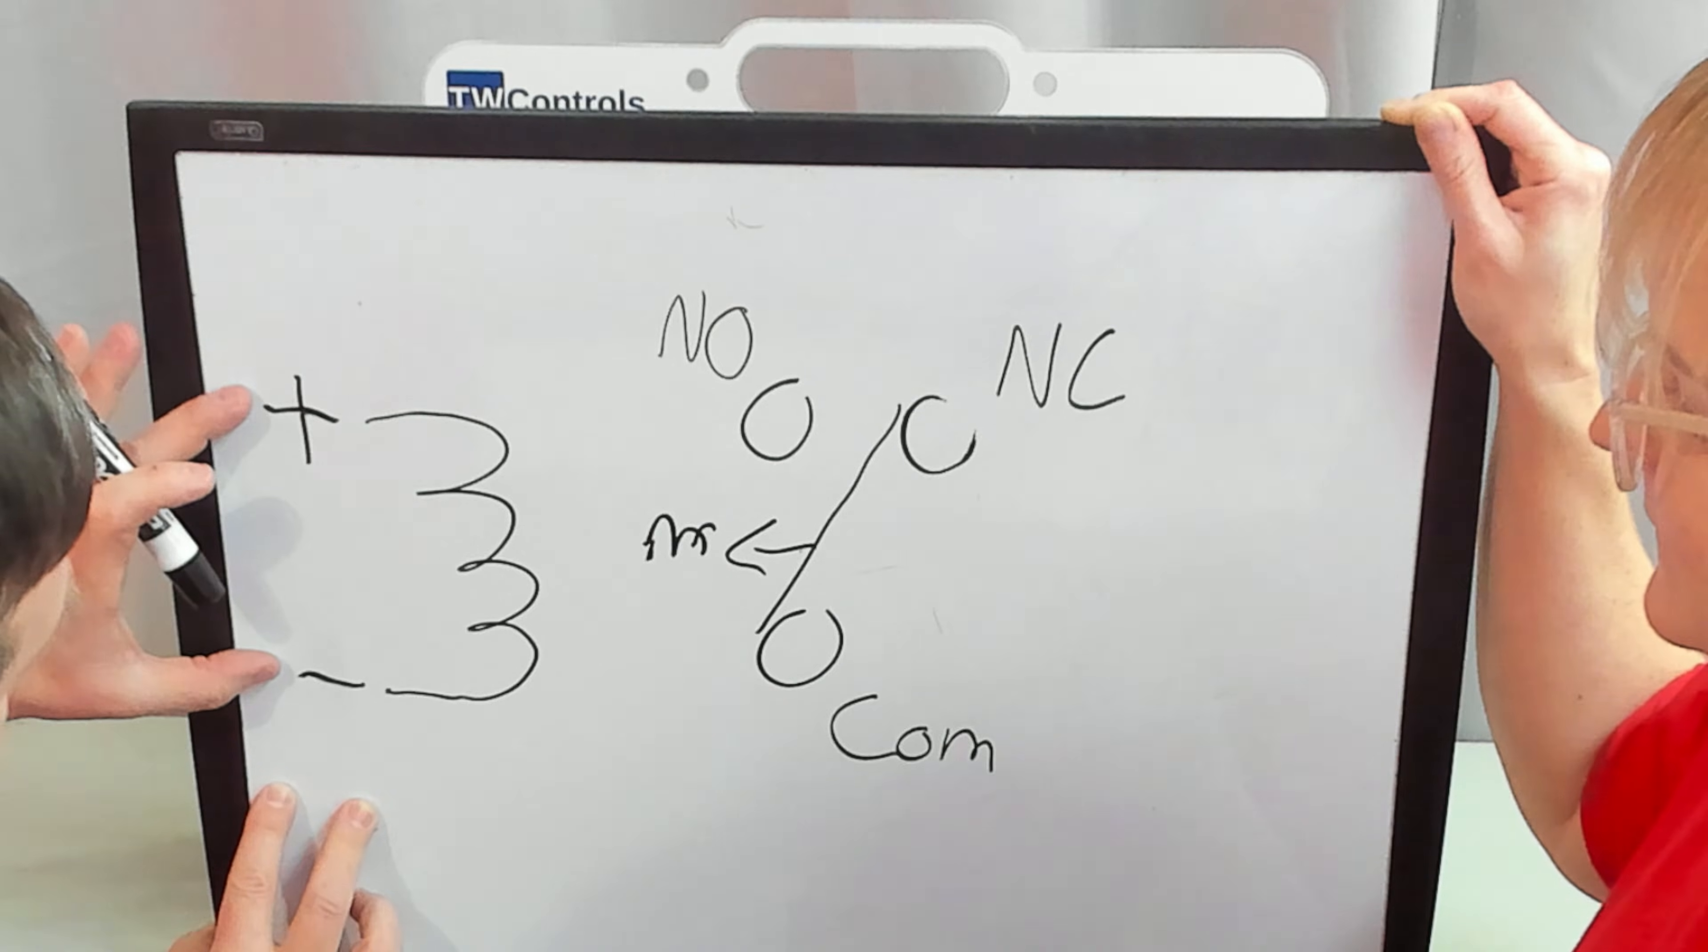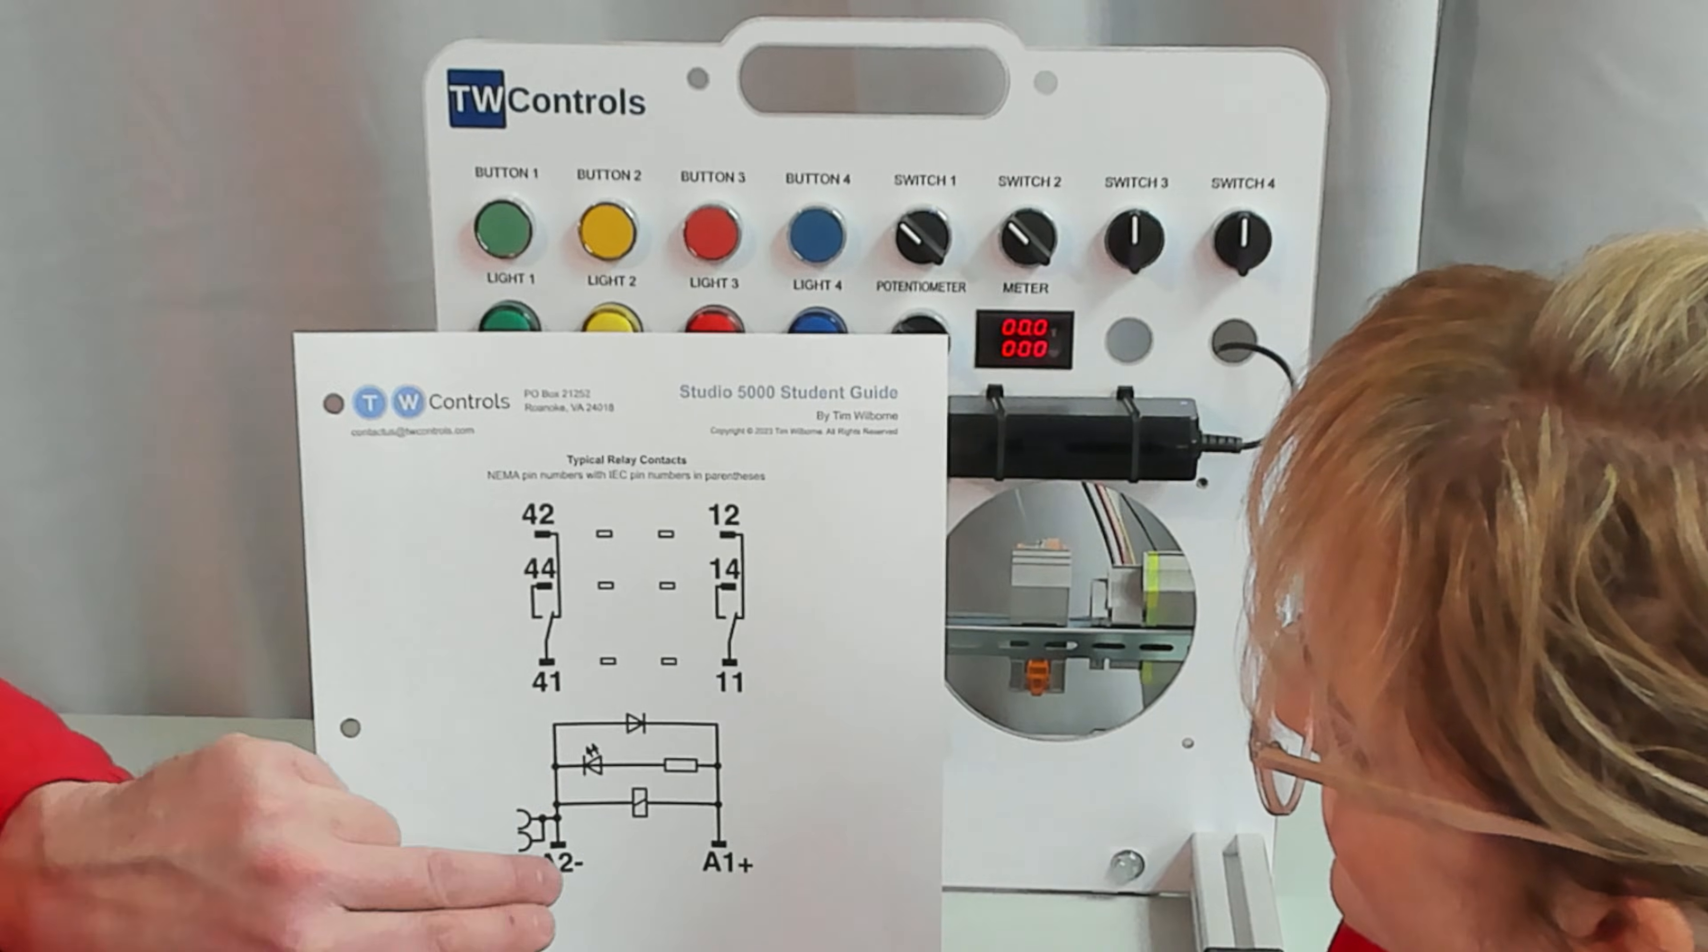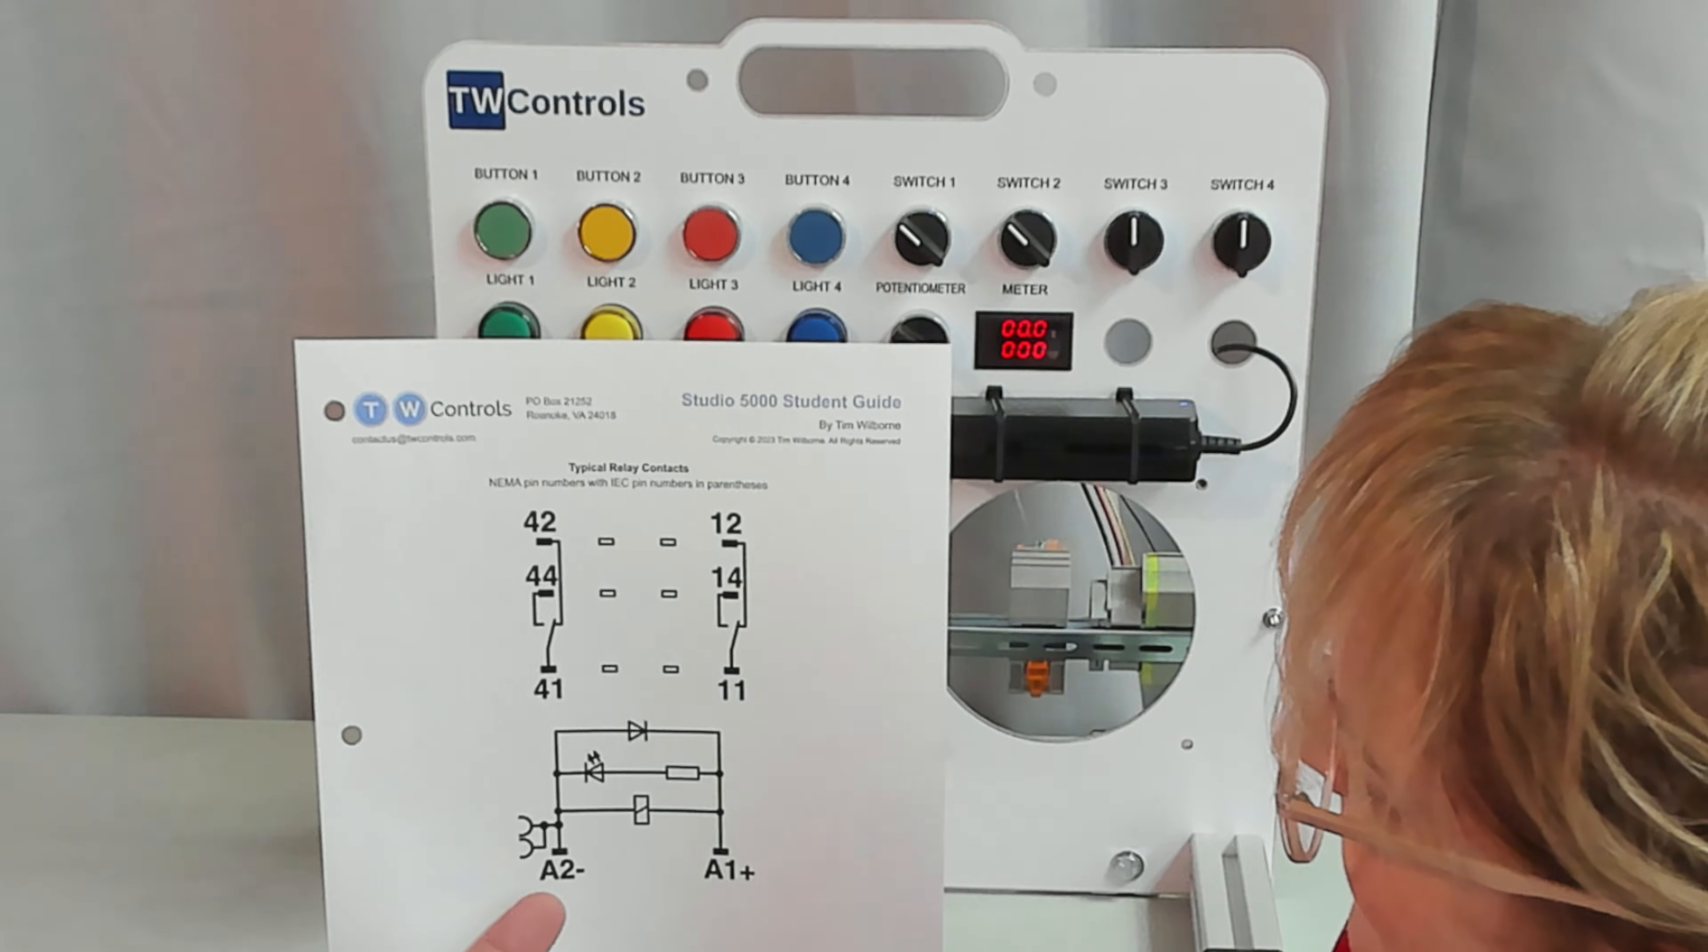So let's start by applying plus and minus 24 volt to our coil. Here's a typical relay diagram. And this bottom part is the coil, and this top part is the contact. So in this case, A1 is the plus, A2 is the minus.